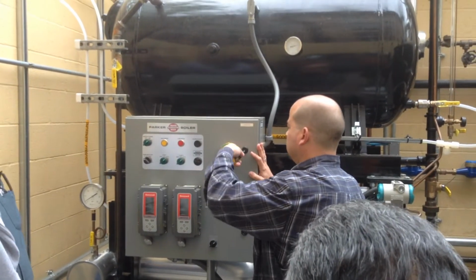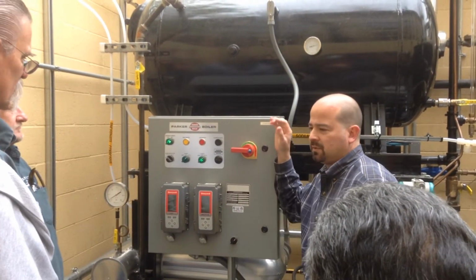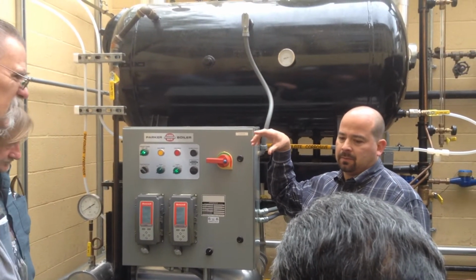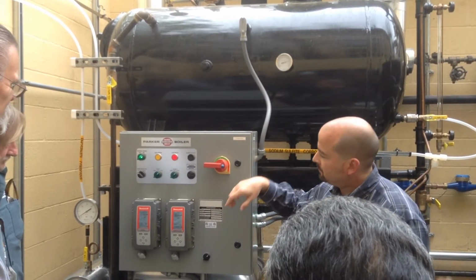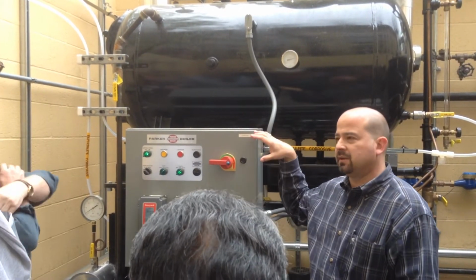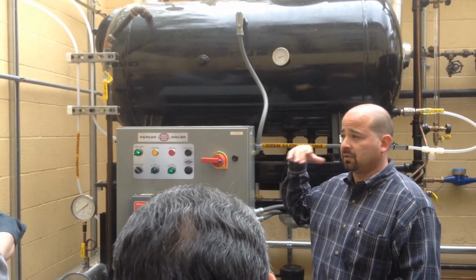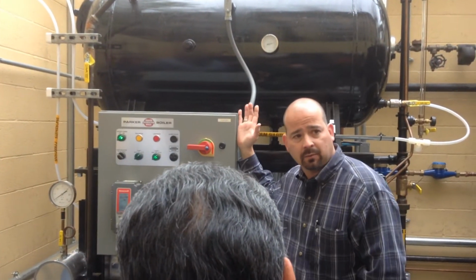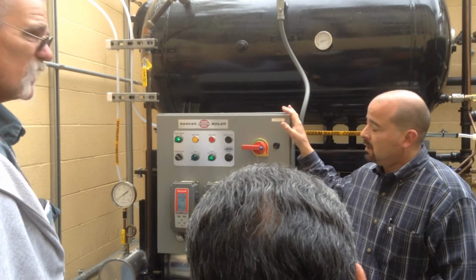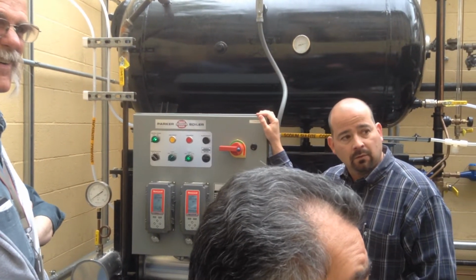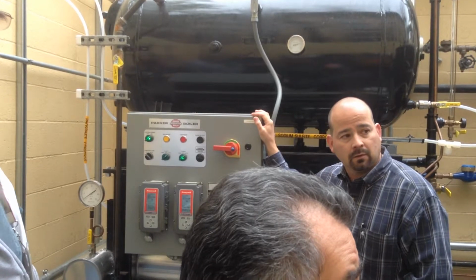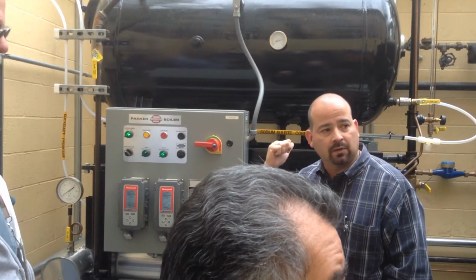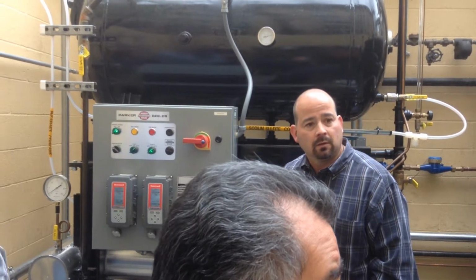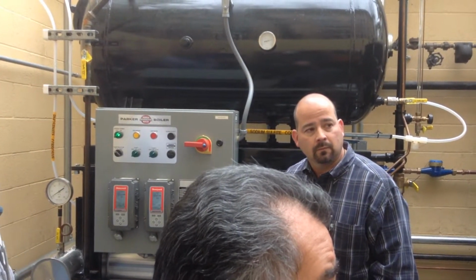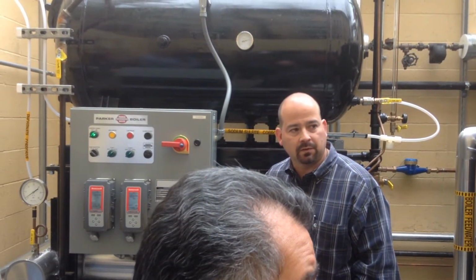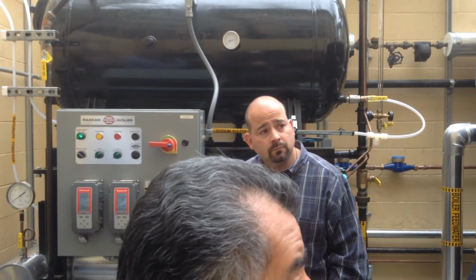Okay. So for the loss of power, I guess we're going to take the secondary side of the control voltage. You've got 480 coming in, is that what you have here? No, we're taking the 120. And then if somebody pulls the power, it's just going to keep the relay energized and it'll send a signal. So if somebody shuts the power off and walks away from it, or we just lose power, we get a Delta V alarm. And then I'll have an alarm here on the pressure.